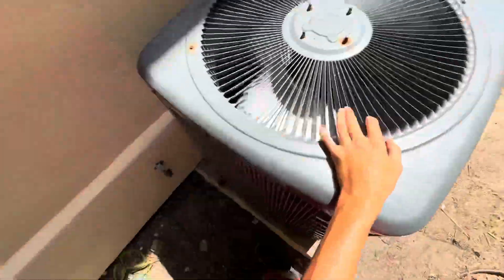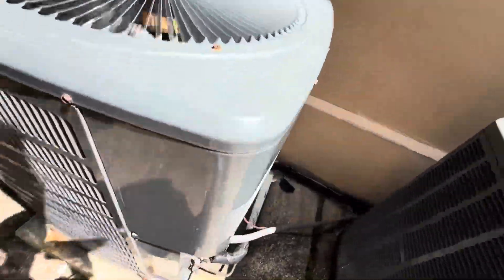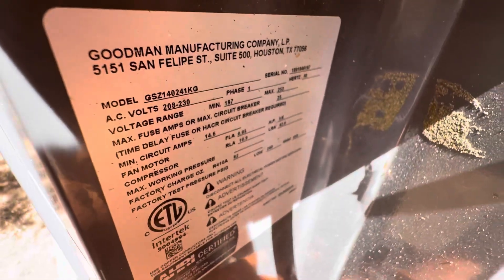Now all three of them are running — well, two and a half, because this one is barely running. Only the fan. No compressor. This is a two-ton GSZ14 from 2018, and the suction line is not showing any temperature, as it should be.